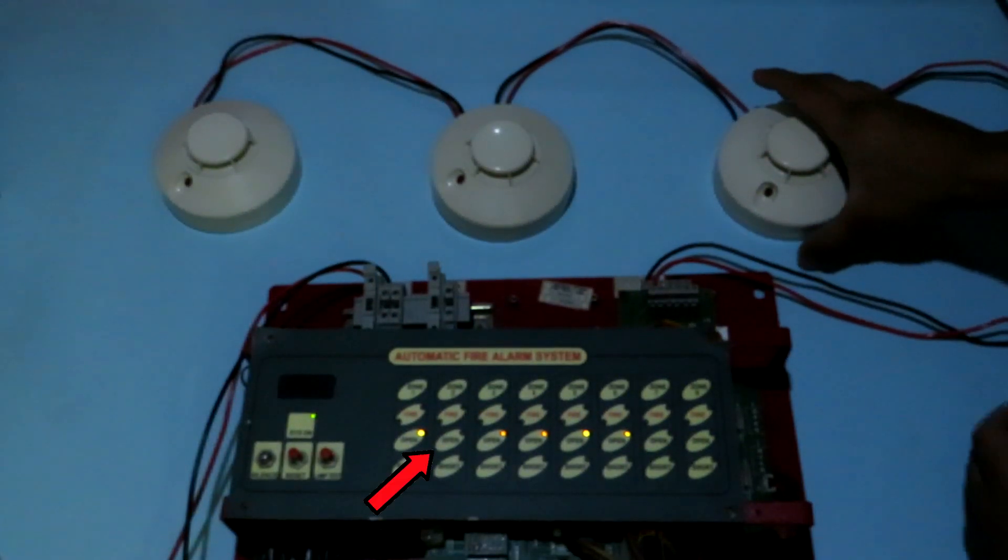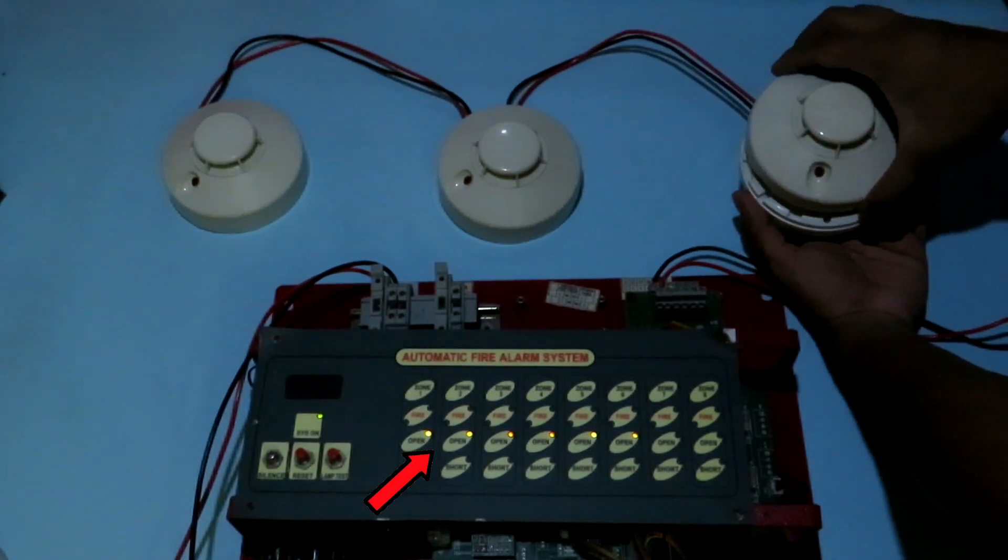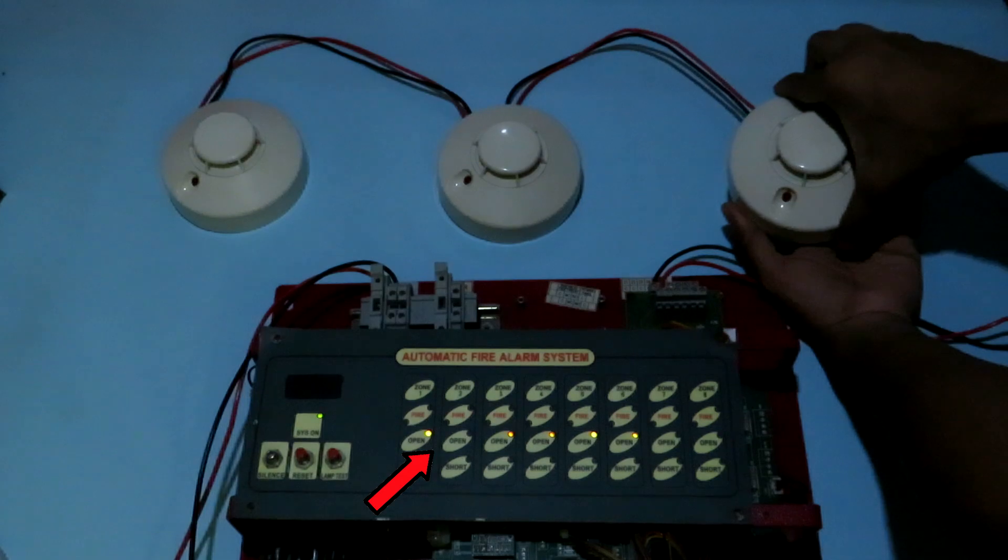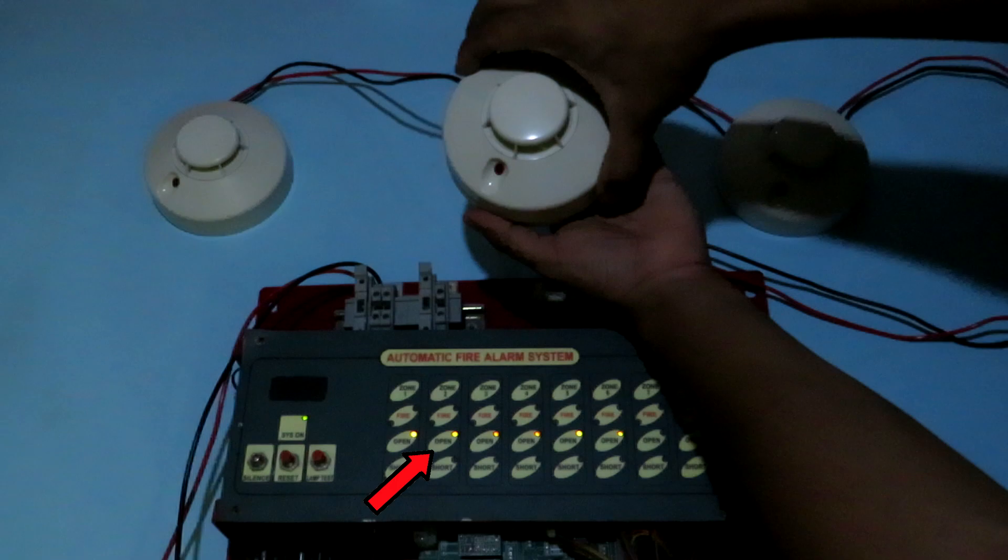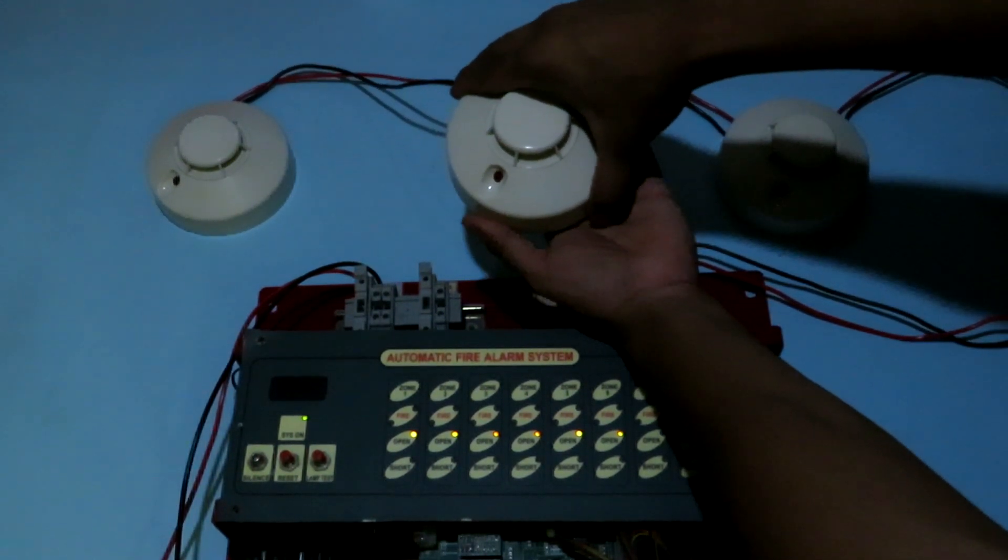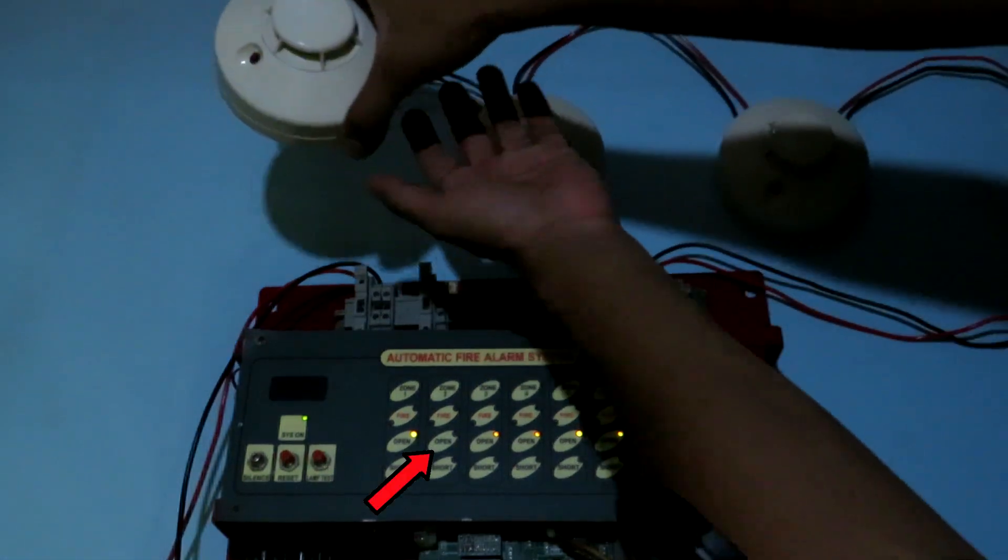The zone loop that we have here is connected to zone number two in this panel. Now you can observe that if we open any detector in the line the open circuit indicator for zone two is switching on. The minute we install back the detector you can see that the open circuit indication at zone two goes off. The open circuit function in the control panel basically tells you that one or more detectors in the line are not connected or that the line is probably damaged or broken at some point due to which all the detectors are not successfully connected to the panel.